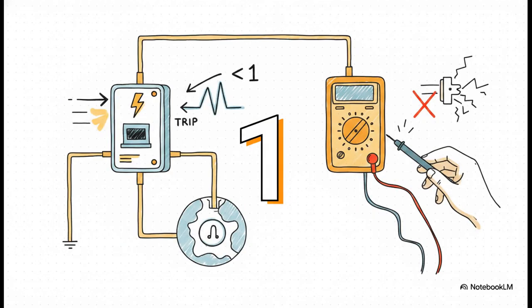1 ohm. This is the magic number when we move further down our timeline to carrying out the earth fault loop impedance test. When you perform this specific test, you must ensure your instrument is set to the high current trip setting, not the low current no trip setting. Using that high current setting, your final result must be less than 1 ohm. Why? Because that incredibly low impedance is exactly what ensures a protective device will rapidly disconnect the circuit during a fault.